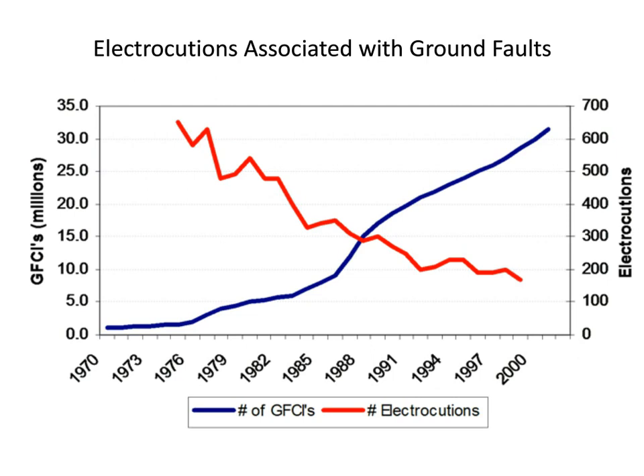Ground fault products were introduced to the marketplace back in the 70s. And this graph that I'm demonstrating here gives you a nice illustration of the correlation between the presence of ground fault safety in the marketplace and the reduction of electrocutions that have happened during that same time period. So as you can see, back in 1970, there was no ground fault, and we had 700 or so fatalities in any given year. Now this chart's a little dated; it only goes out to about 2000, but this really does a nice job of planting the seed as to what is UL's focus with ground fault, and when we get into the discussion on ground fault receptacles, you'll understand where they're driving.